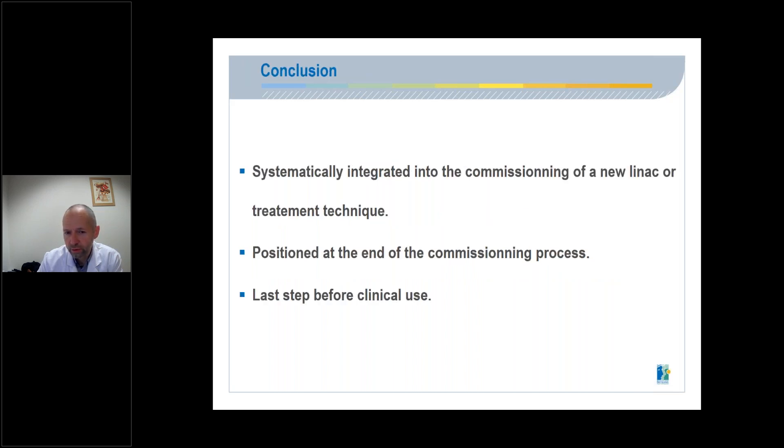To conclude, this QA is systematically integrated into the commissioning of a new LINAC or treatment technique. It is positioned at the end of the commissioning process, and it is the last step before clinical use.